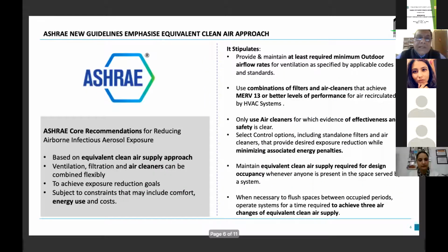And the recent new ASHRAE guidelines, which have been issued only last month, prominently highlight the equivalent clean air supply approach, because the ASHRAE core recommendations for reducing airborne infectious aerosol exposure are based on the equivalent clean air supply approach, which depends on ventilation, filtration, and air cleaning technology, subject to the constraint that the energy should not increase exorbitantly. So that is the flexibility that has been provided now to manage the outdoor air requirement.